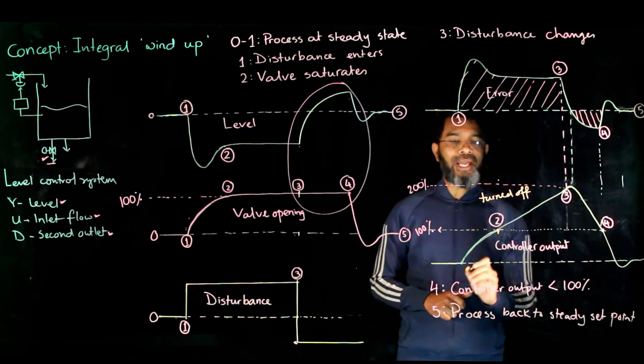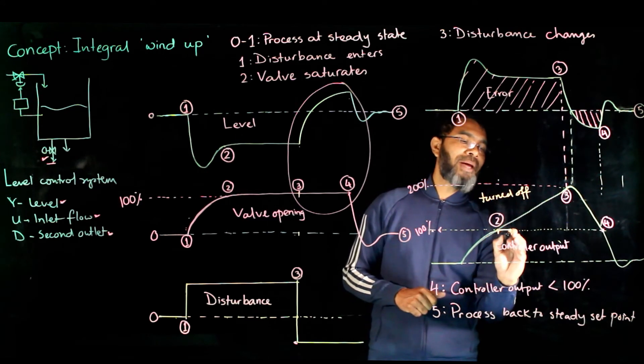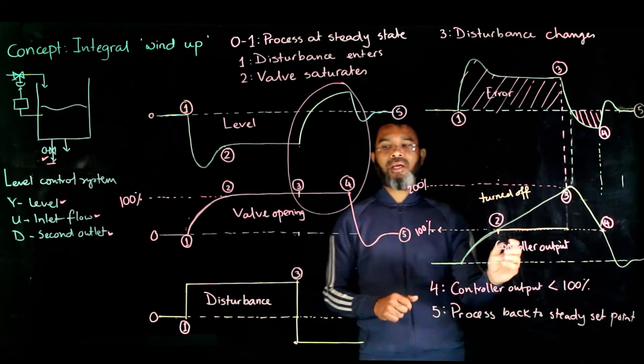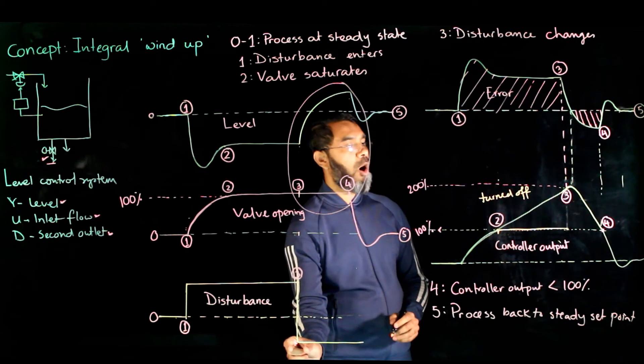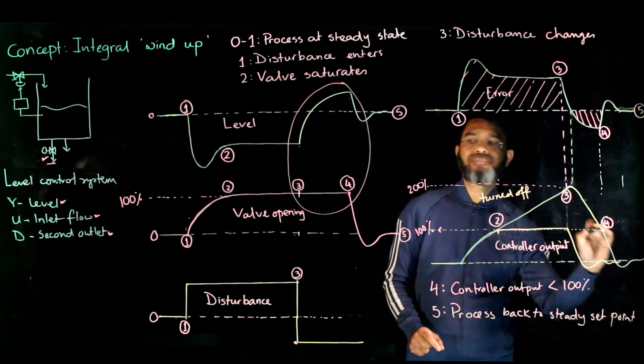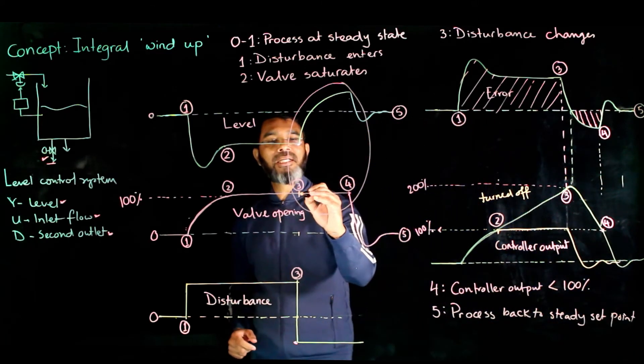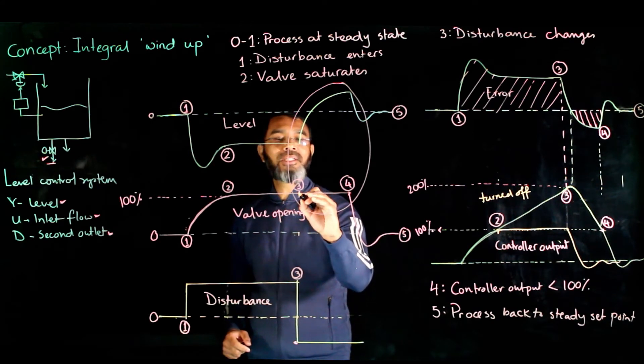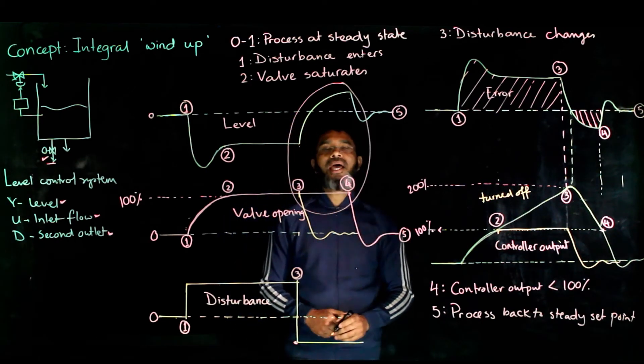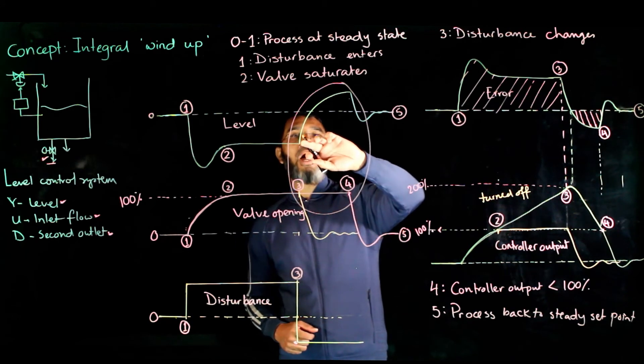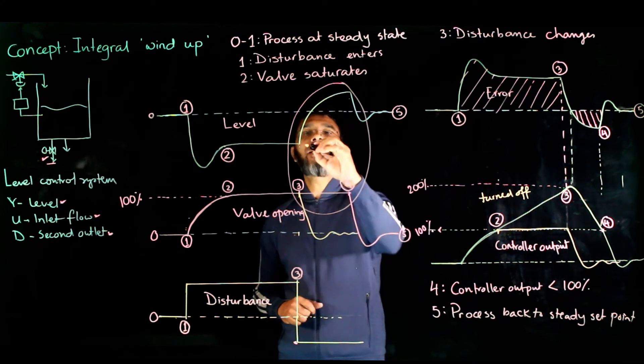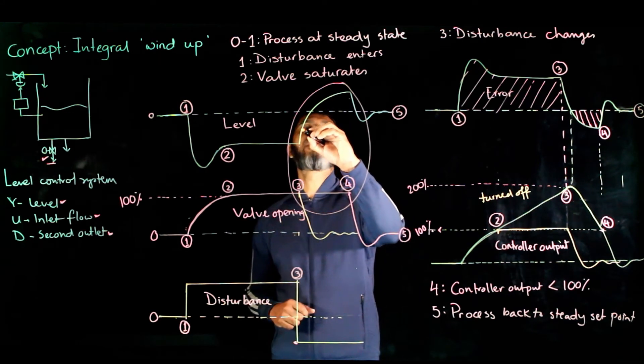To get rid of the windup, the integral action is turned off, meaning the value remains at 100%. In that scenario, whenever the disturbance moves in the opposite direction, the controller would be able to take action. The valve would start closing at instant 3, and the output would not go beyond the desired value but would instead stabilize around the set point.